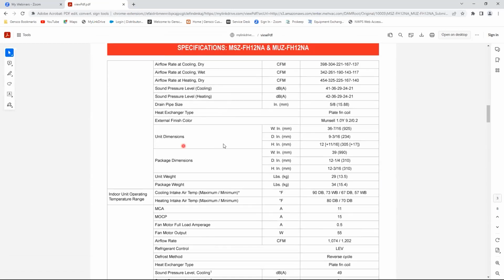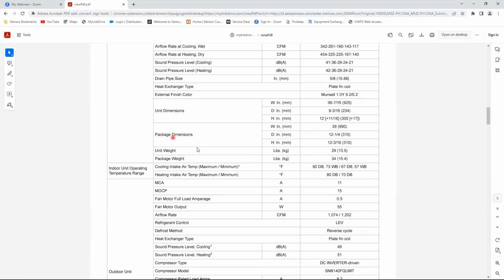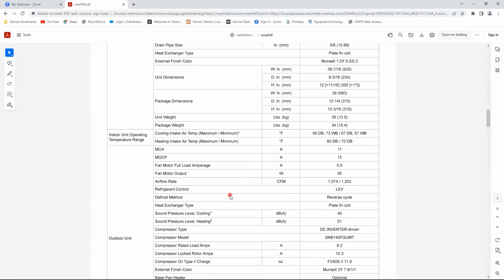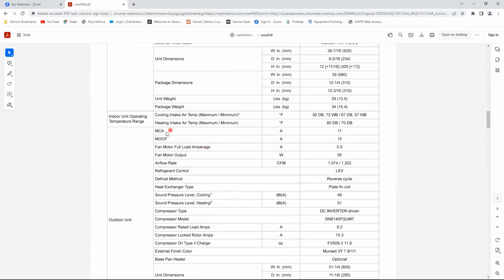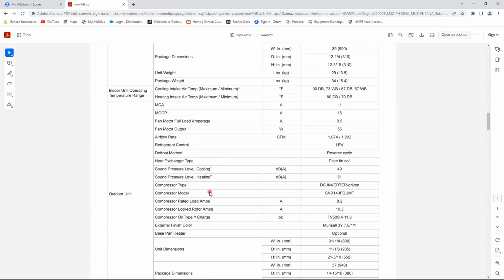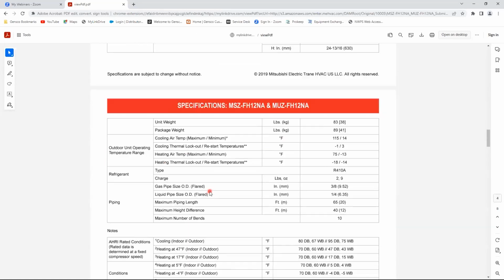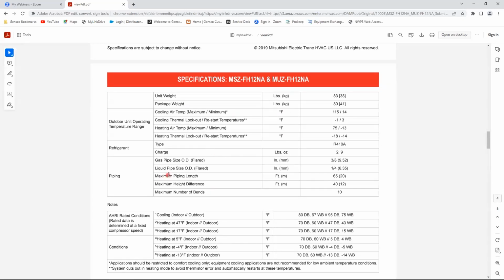And then we have all of our diameters. If you're wondering how big a unit is, come here — it actually gives you the package dimensions and the unit dimensions themselves, the weights, your minimum circuit amps, max overcurrent protection, your amp draws, airflow, and down here, refrigerant type and your piping size.